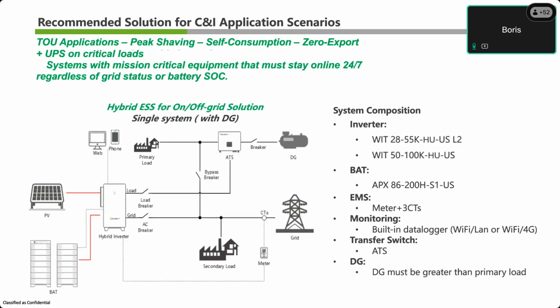Showing the same on-off grid, but with a diesel generator. We do not offer an ATS, but there's third-party ATSs that we can help size for you. The thing that is noteworthy though is that our inverter can handle the control to that equipment. So in the event that you have a mission critical load that cannot go offline no matter what, or if the batteries die and the grid's offline for too long, then you can have a diesel generator in there, and we can provide the output to that diesel generator to turn it on and off based on the state of our APX battery. And this, I'm not showing it, but it can be done in parallel as well.